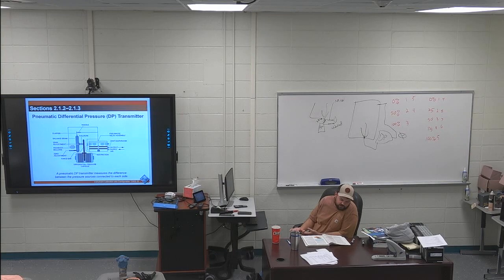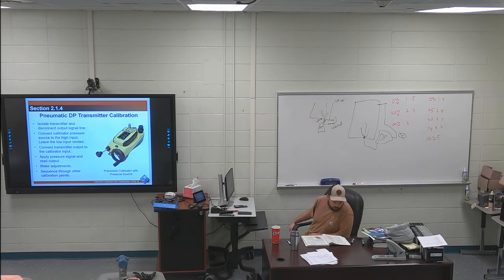Page 12, pneumatic calibration process overview 214. Step 1 is highlighted on page 12. Step 1 is isolate the transmitter from the process by coordinating the isolation process with the proper operations personnel. This usually involves operating a loop and controller in the manual position. Never, ever take something out of service without telling your operator. It's a bad day. They're going to see something on their screen go to 0 and they're going to freak out. Never do anything without talking to your operators. It's a good way of getting operators to not like you. Always go talk to your operator first. Should be obvious. You can read through the steps of that if you want to. I don't have anything else highlighted.